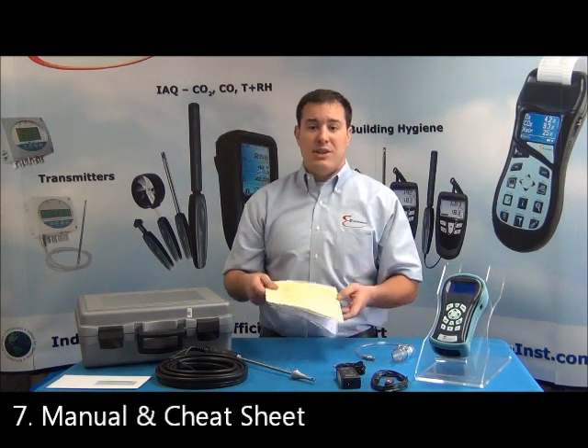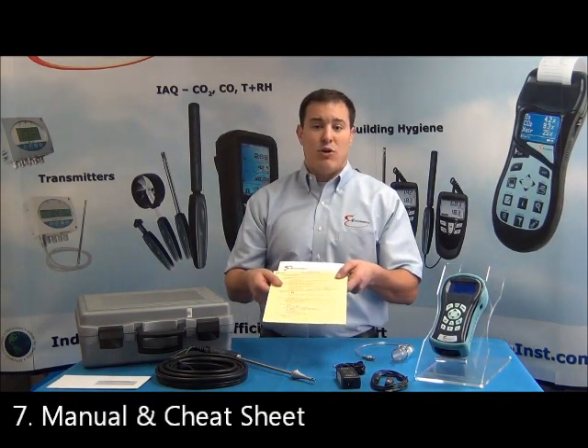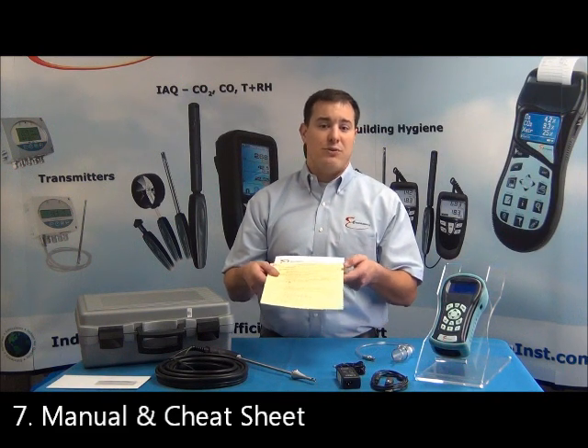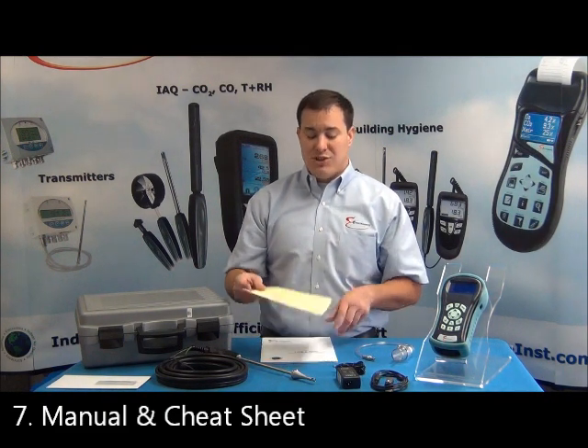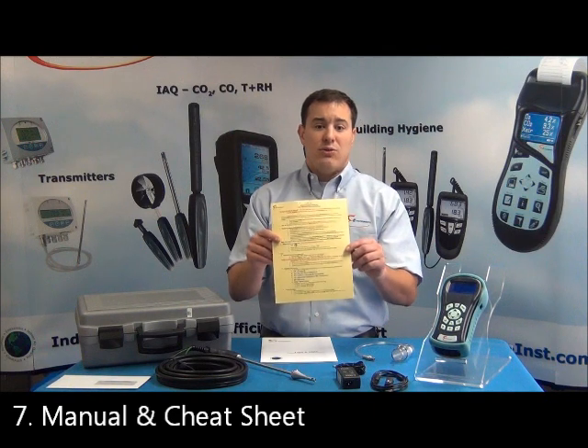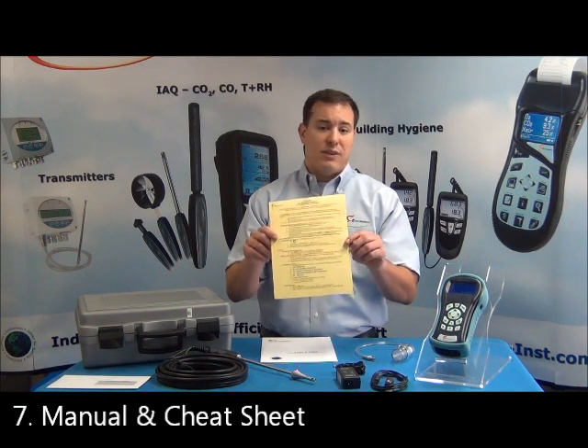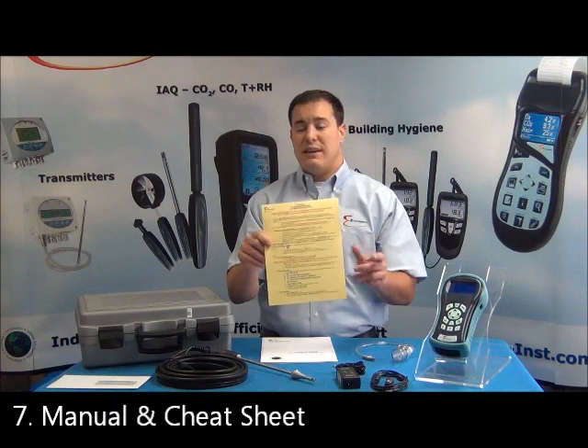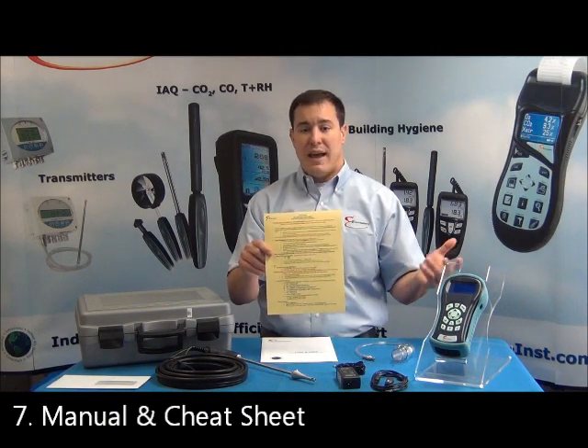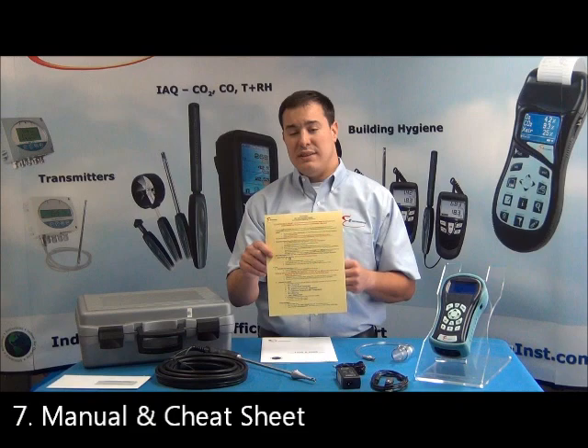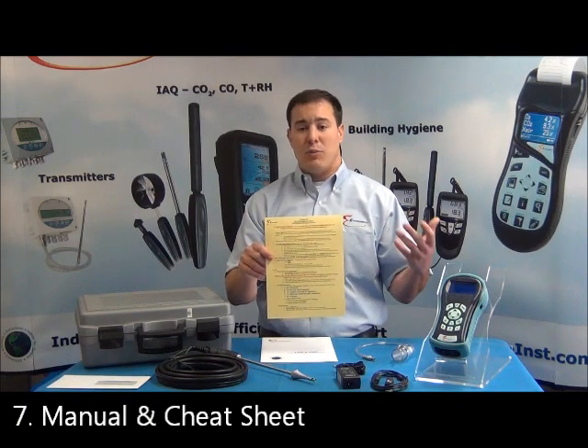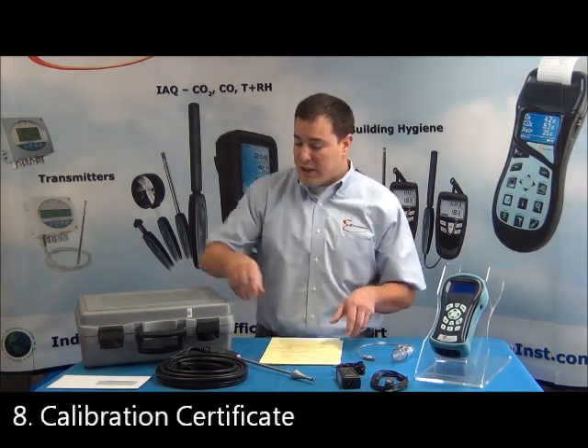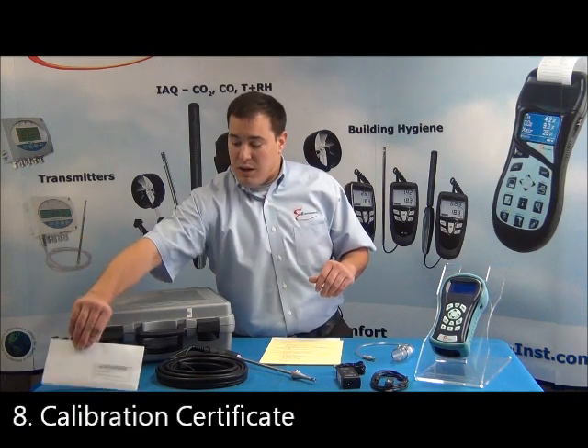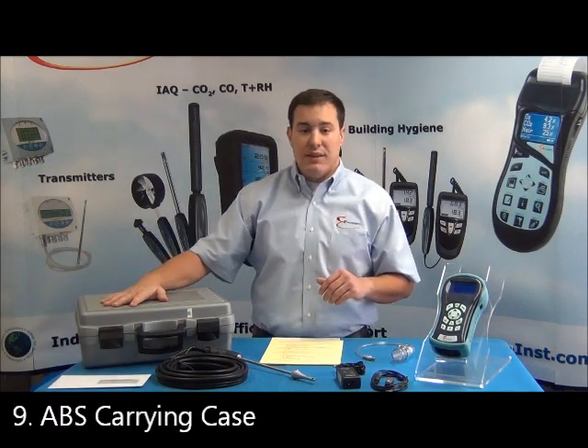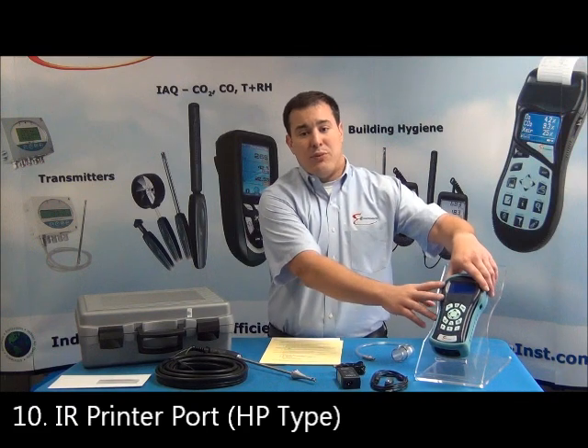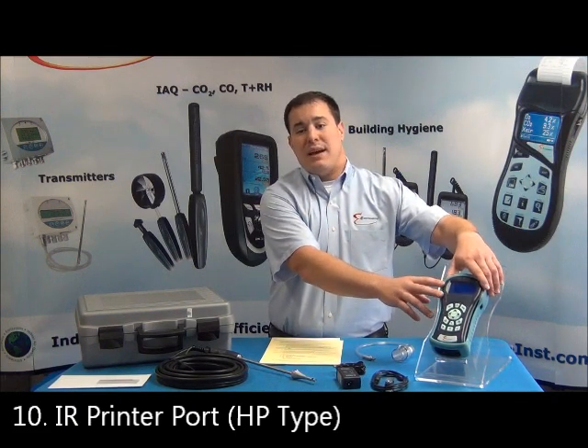The manual and cheat sheets. This user-friendly manual incorporates many photos and flowcharts for easy interpretation. The one-page cheat sheet also gets the user very easily familiar with the analyzer and how to turn it on, connecting the probes, setting the fuel and oil, taking the draft or gas pressure test, taking your combustion efficiency test, and saving, downloading, or printing the final report. Your calibration certificate, a protective ABS carrying case, and an IR printer port to print to any HP type infrared printer.